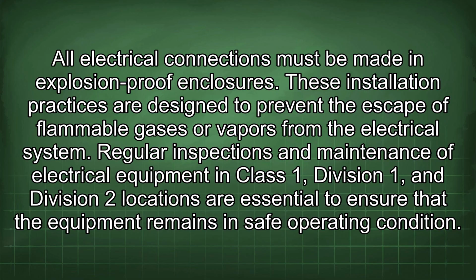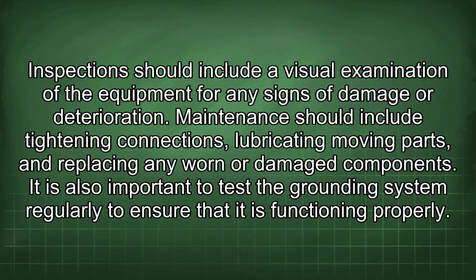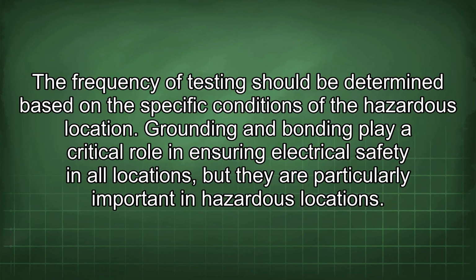Regular inspections and maintenance of electrical equipment in Class 1, Division 1, and Division 2 locations are essential to ensure that the equipment remains in safe operating condition. Inspections should include a visual examination of the equipment for any signs of damage or deterioration. Maintenance should include tightening connections, lubricating moving parts, and replacing any worn or damaged components. It is also important to test the grounding system regularly to ensure that it is functioning properly. The frequency of testing should be determined based on the specific conditions of the hazardous location.